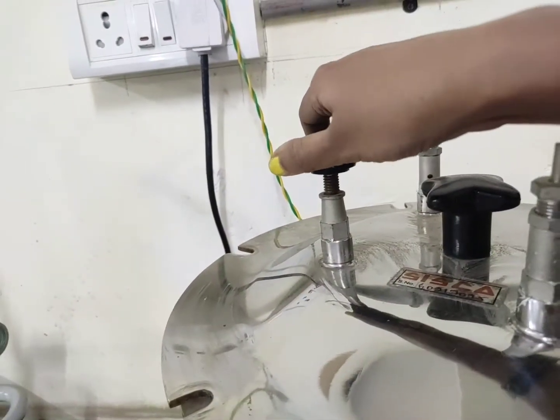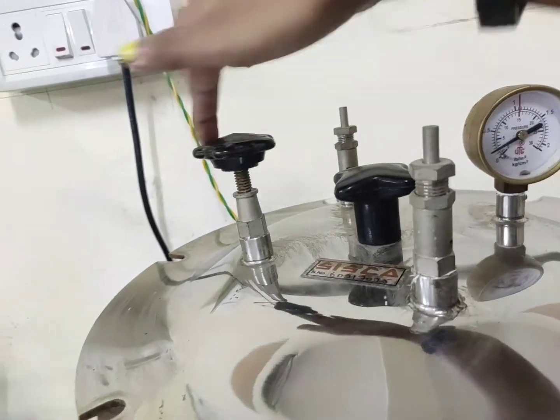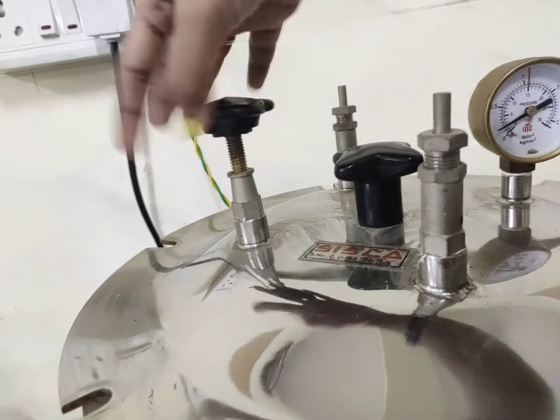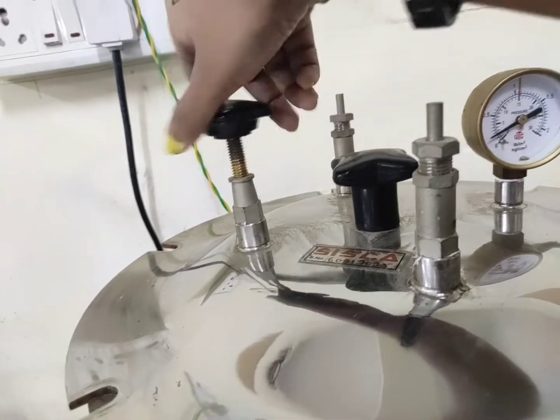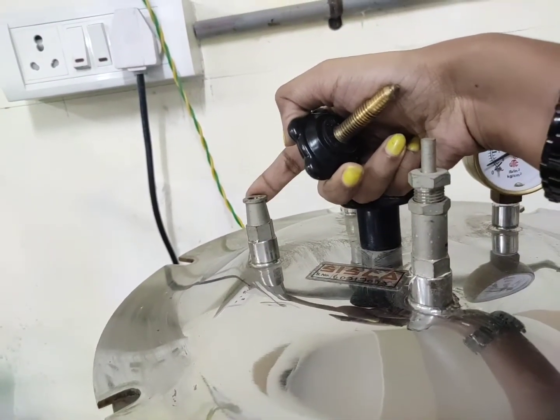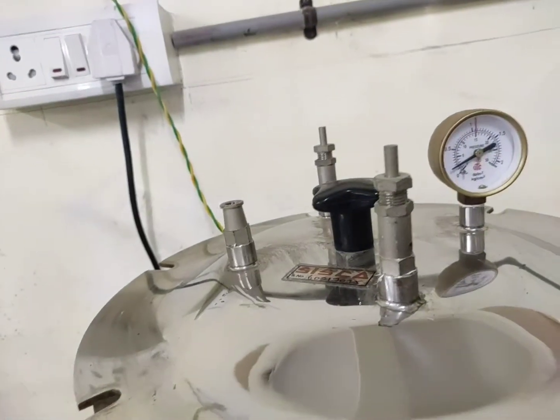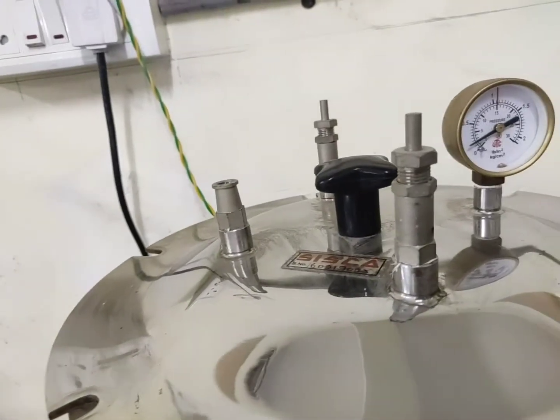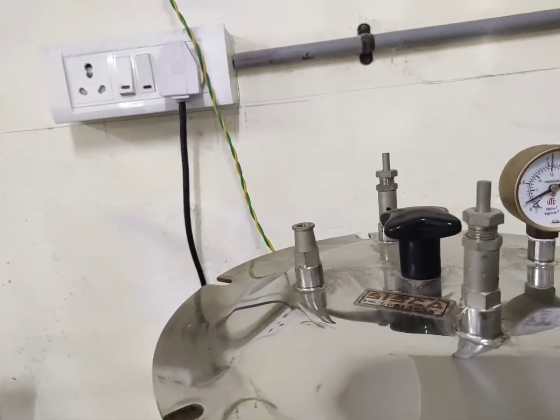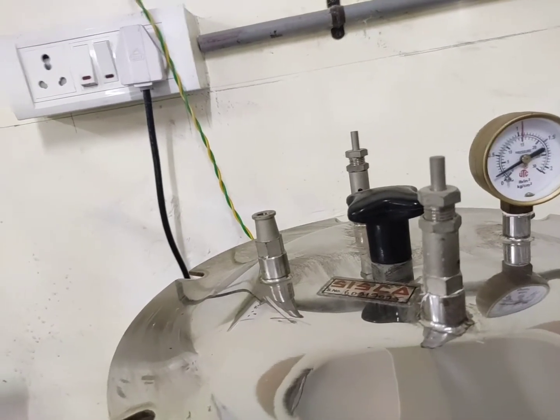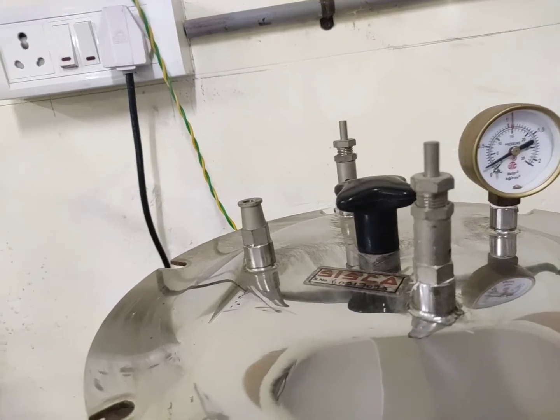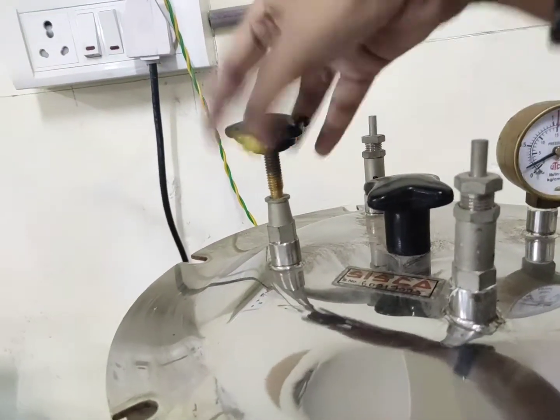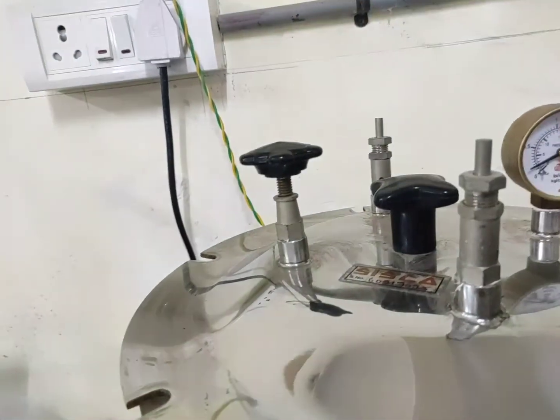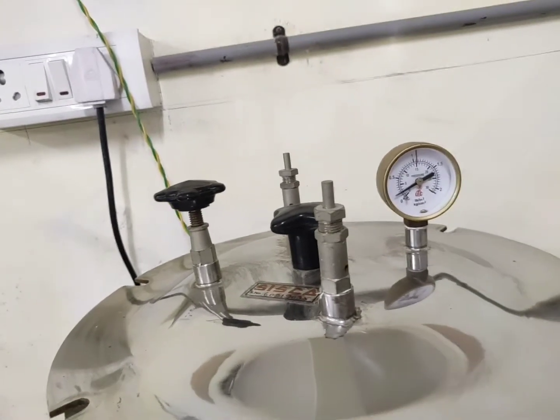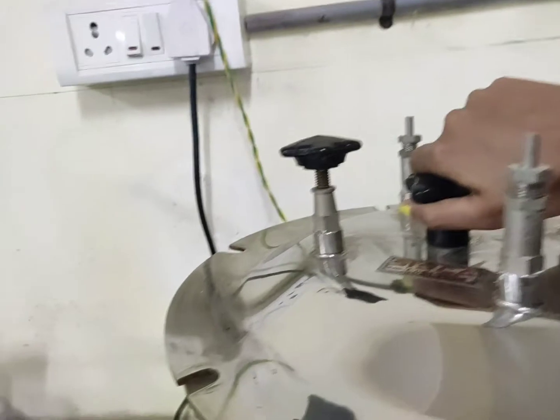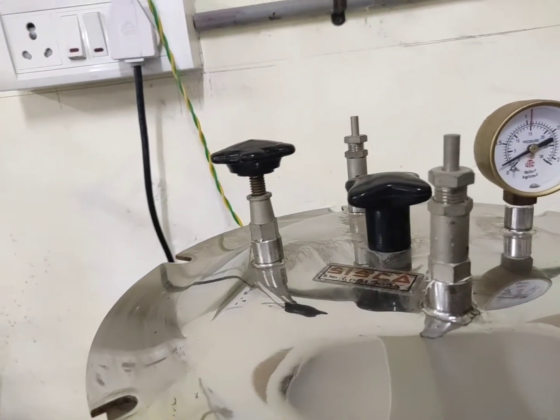Now this is the one which, as I have mentioned, is used in the sterilization. The first stage of sterilization is purging. That means whatever cool air is present when you are starting the instrument has to be removed. In order to do that, this steam release valve or pressure release valve is given. Once you start the instrument, you have to wait at least 10 minutes, so that the entire air present inside is removed and it is filled with the steam that will be generated inside. Once the purging is over after 10 minutes, you can close it back, and then your sterilization process will start, where your temperature and pressure will increase till 121 degrees centigrade or 15 pounds. Okay, and this is only to hold the lid and just to lift it. So these are the basic things of this autoclave.